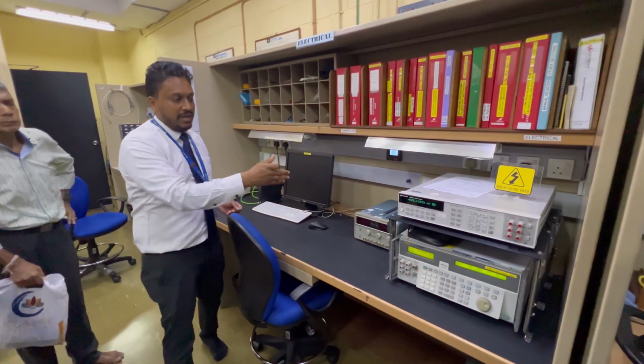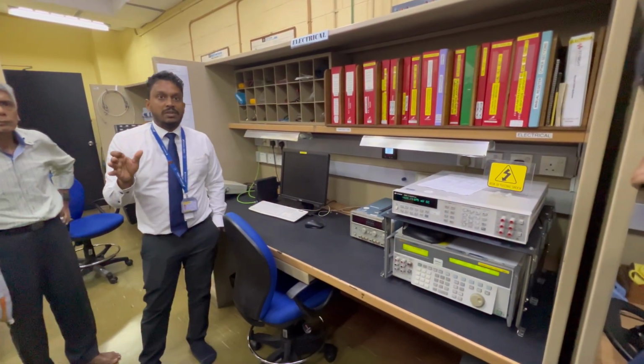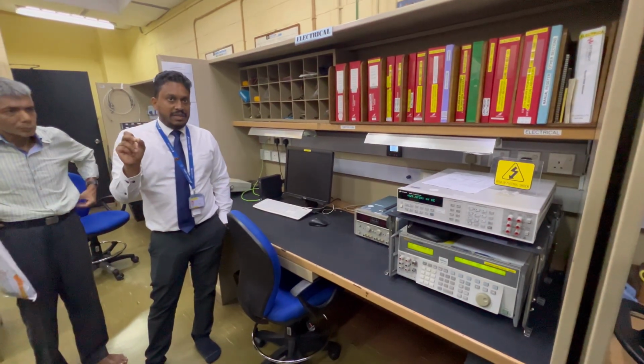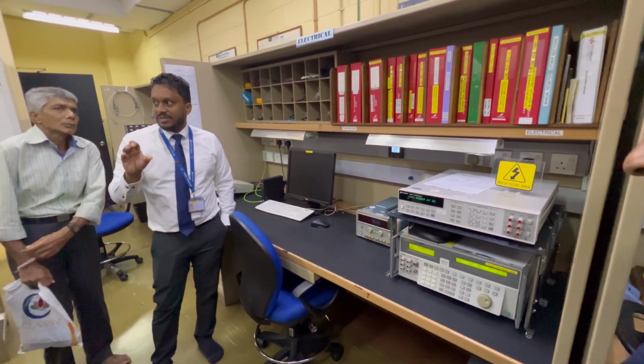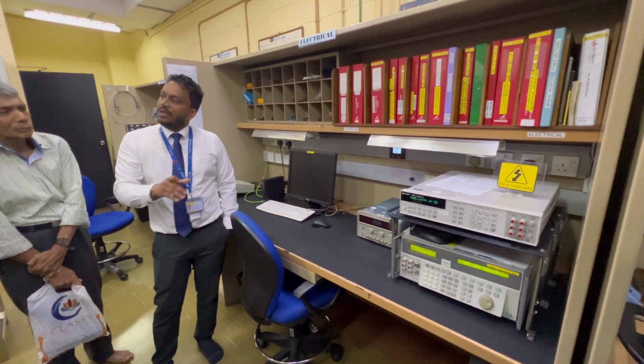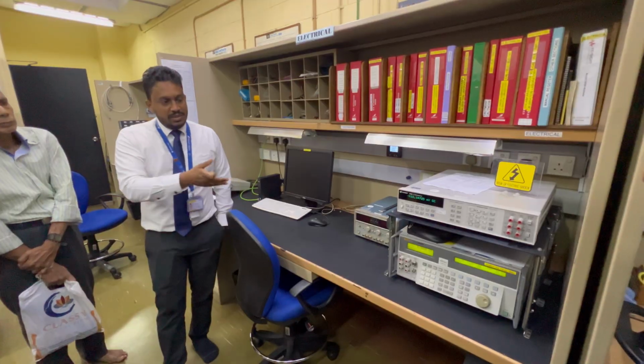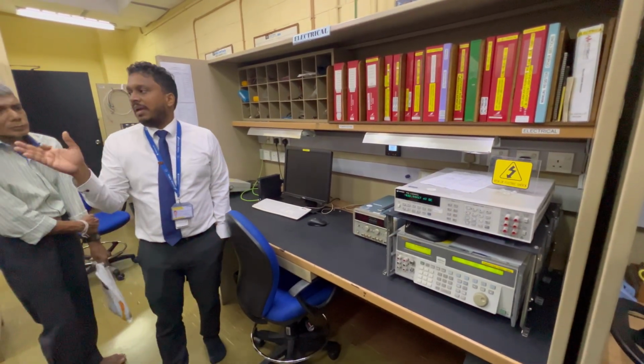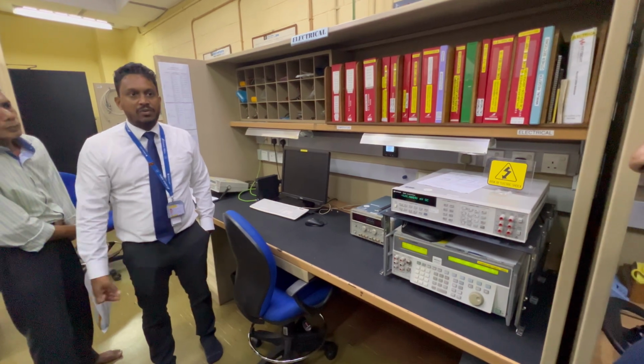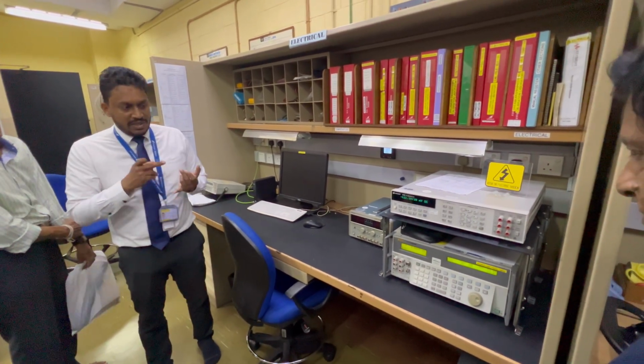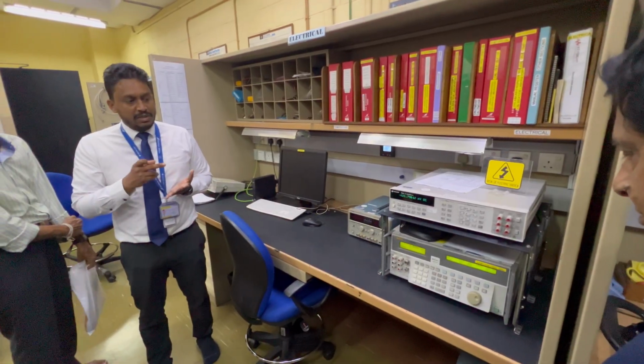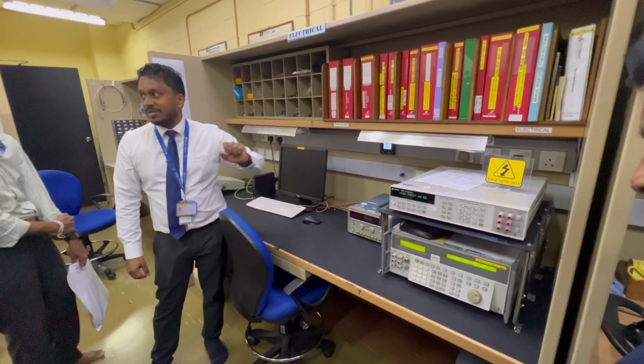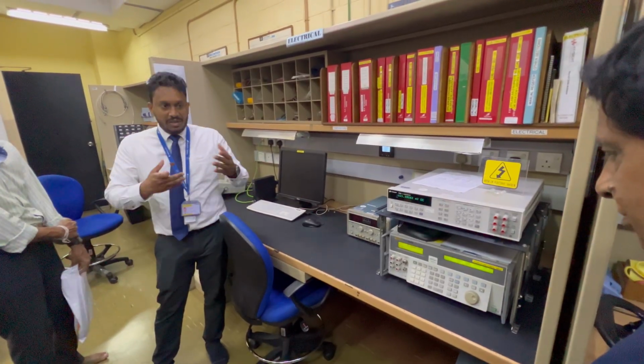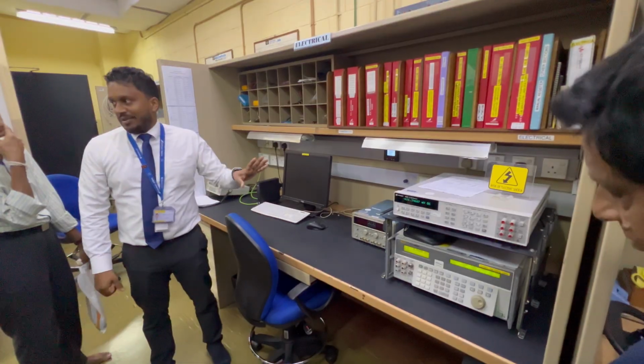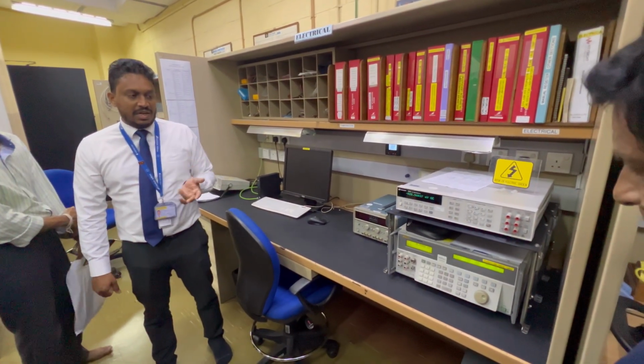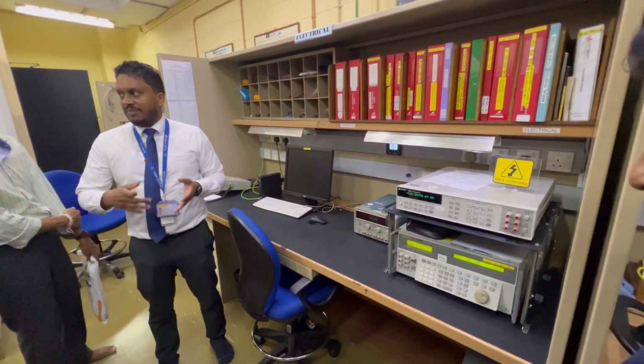Now, this equipment can go from DC 0 to 1020 volts, DC or AC. So we are accredited to source AC voltage from 0 to 1020 volts. Most of the multimeters start from 1000, so I think we have the capability to calibrate 90% of them. You name it, any of the multimeters. Apart from voltage, it can source AC and DC current. This one is actually fully capable of calibrating oscilloscope pulse. It can look at the signals any way you want, but we are not using it. We are using it for resistance and AC, DC current. Now we are going to go for LCR meters also if there is a requirement.